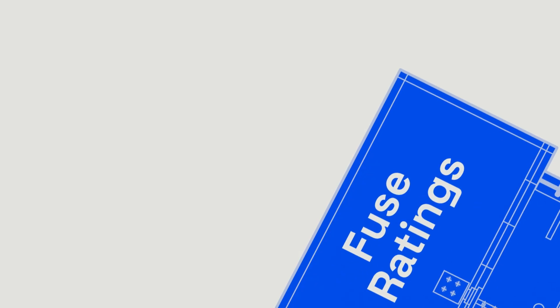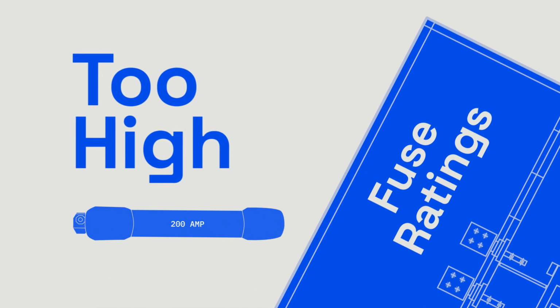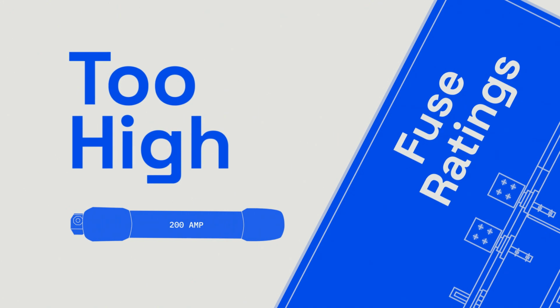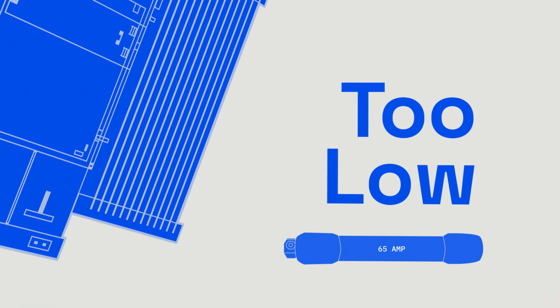For example, if your fuse ratings are too high, the fuse won't clear the fault fast enough and can lead to damage of your equipment. Too low, and you can get nuisance trips, headaches, and unnecessary outages. So you'll always want to coordinate fusing with both your upstream and downstream devices.